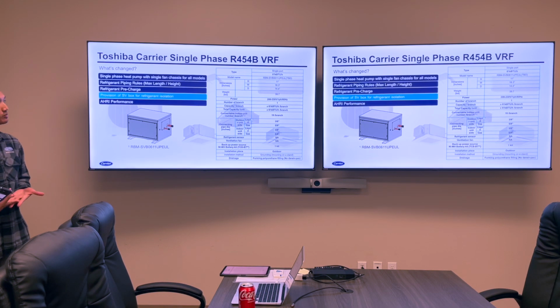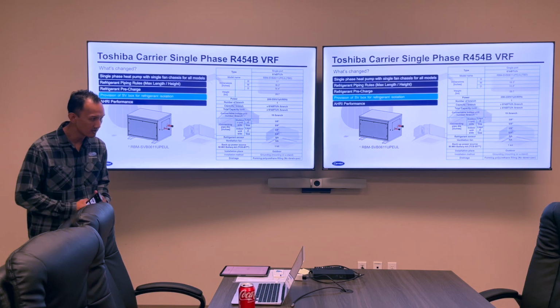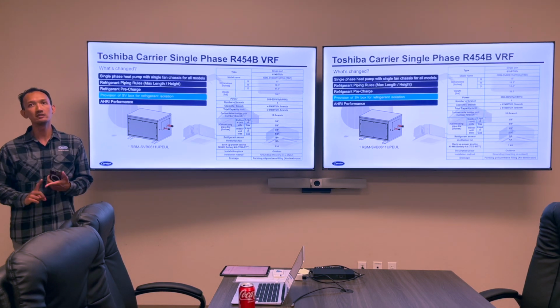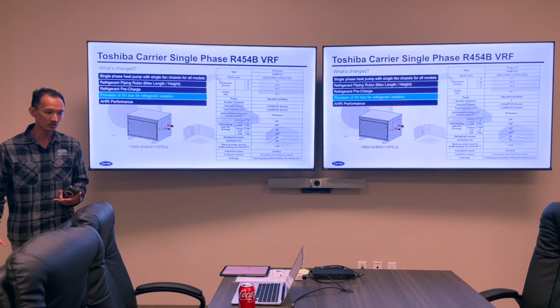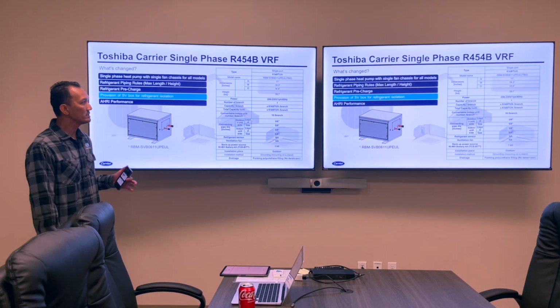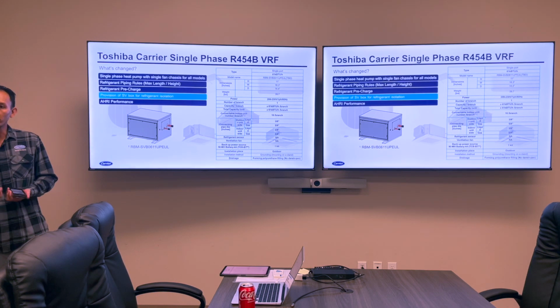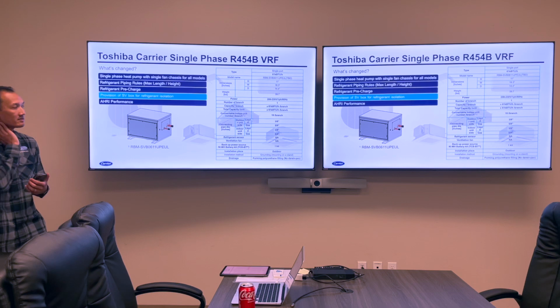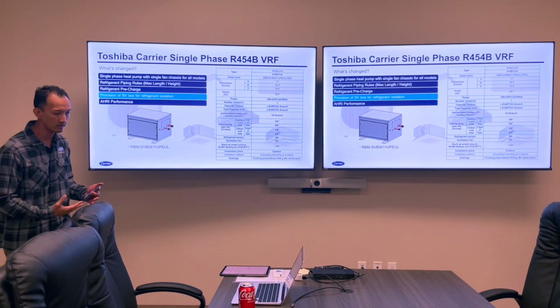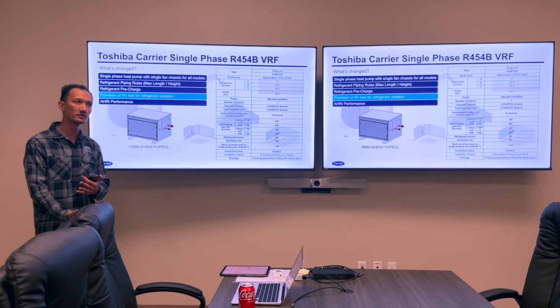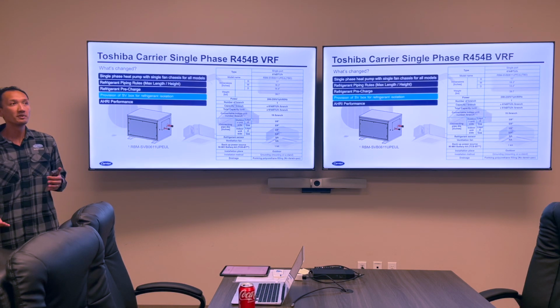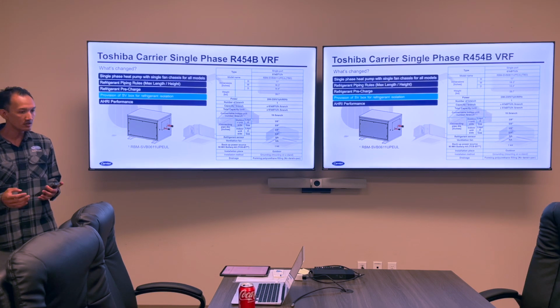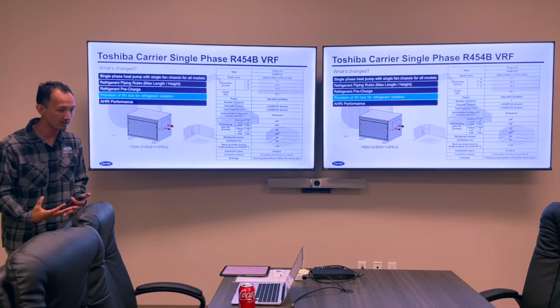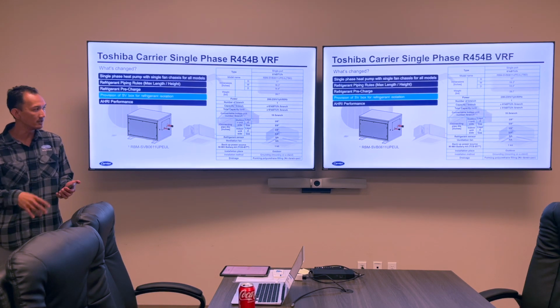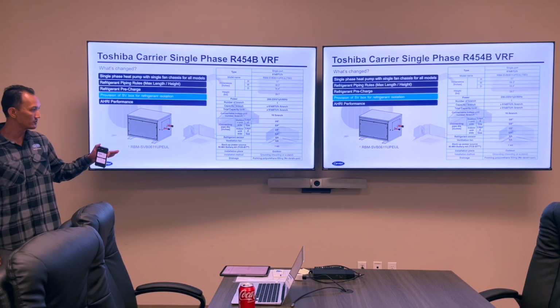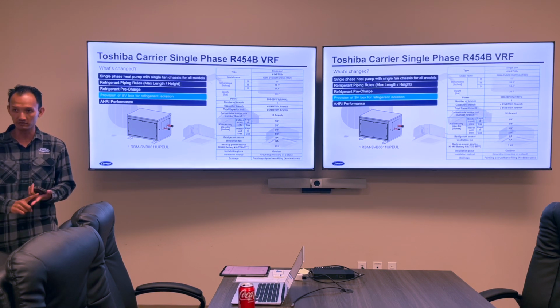Now, with the A2L refrigerants and some of the issues that we have to deal with in terms of flammability and making sure occupants are safe, we introduced this SV box, solenoid valve box. So for systems, especially on our single phase where you have multiple fan coils, long refrigerant line lengths, where the potential for a leak to occur and dump all that refrigerant into a space, depending on ASHRAE compliance, we may need to introduce these SV boxes to help mitigate the amount of releasable charge.